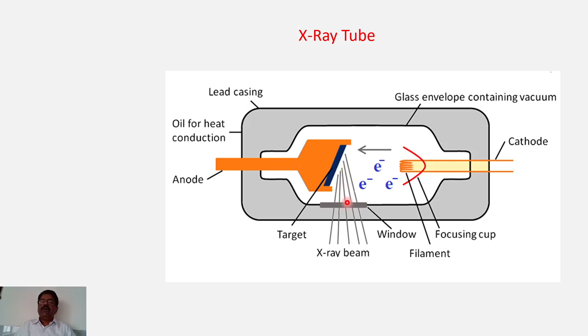So let us see now how this works. Because of this low tension supply applied to the filament, electrons are emitted. The anode is kept at very high positive potential. Therefore, the electrons will be accelerated, attaining a very high kinetic energy because of the high positive potential at the anode. So they travel towards the target material. When they enter the target material with a very high kinetic energy, the electrons inside the target material are rearranged. During this rearrangement of the electrons, X-rays, then unknown rays, are given out of this target material. These are called X-rays. So this is how the X-rays are produced in a typical X-ray tube.